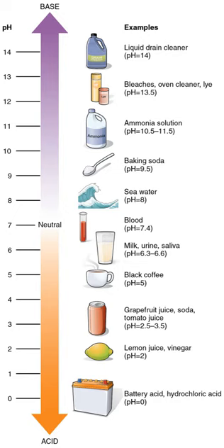Topic: Extremes of pH. Measurement of pH below about 2.5 (approximately 0.003 moles dm-3 acid) and above about 10.5 (approximately 0.0003 moles dm-3 alkaline) requires special procedures because, when using the glass electrode, the Nernst law breaks down under those conditions. Various factors contribute to this.